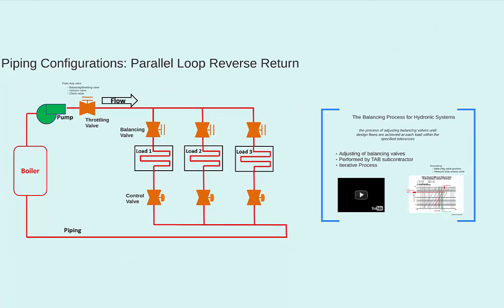Now, the chart just shown has the term circuit setter in the title. This may be a term you have heard before. Often people refer to both balancing valves located at the coils as well as throttling valves located at the discharge of the pump as circuit setters. But circuit setter is a brand name for a series of balancing valves manufactured by Bell & Gossett. It is probably the most commonly used balancing valve, but it is not the only one out there. So the generic use of circuit setter is like someone calling a tissue a Kleenex. Technically, not all tissues are Kleenex, and technically, not all balancing valves are circuit setters.